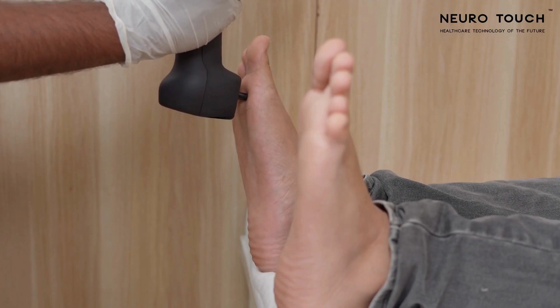Take feedback from the patient. When the probe is placed on the test point, the patient should feel a mild vibration. If the patient can't feel the mild vibration, increase the voltage by clicking the up key. Place the probe again on the same test point and take feedback from the patient.